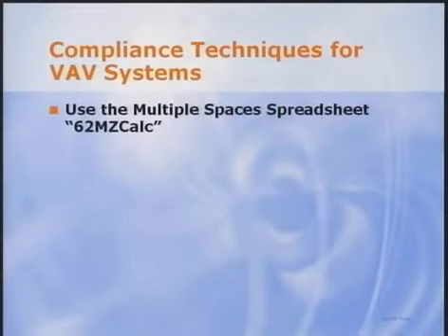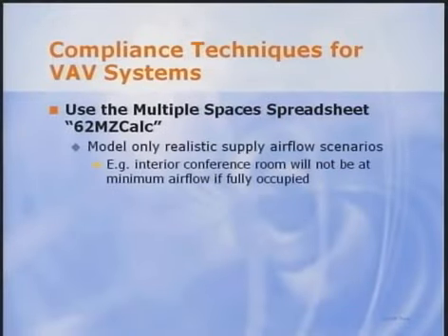For example, take an interior conference room. A conservative engineer might assume that the space is fully occupied and yet the VAV box serving the space is at its minimum set point. But that's not realistic. A more realistic but still conservative scenario is that everyone is present, the lights are on, but there are no plug loads such as an LCD projector or a PC you designed for. Assume they're off. A simple load calculation can be used to determine the resulting airflow rate. That rate, not the zone minimum, should be used in the spreadsheet.